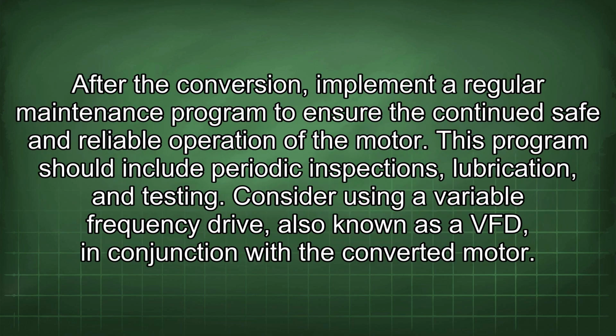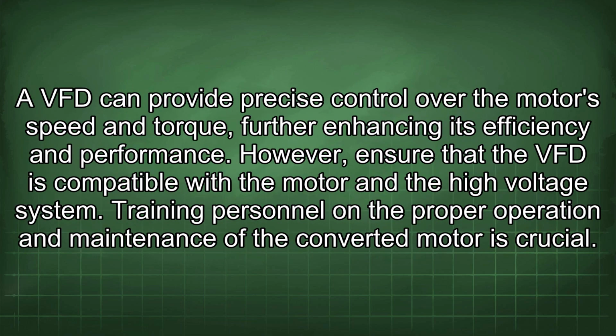After the conversion, implement a regular maintenance program to ensure the continued safe and reliable operation of the motor. This program should include periodic inspections, lubrication, and testing. Consider using a variable frequency drive, also known as a VFD, in conjunction with the converted motor. A VFD can provide precise control over the motor's speed and torque, further enhancing its efficiency and performance. However, ensure that the VFD is compatible with the motor and the high voltage system.